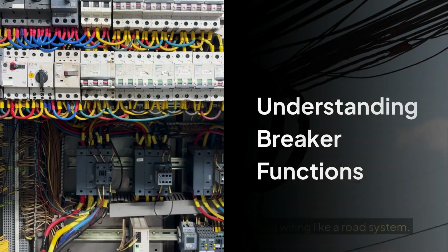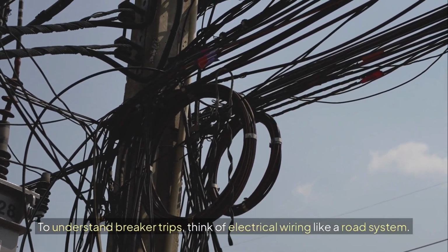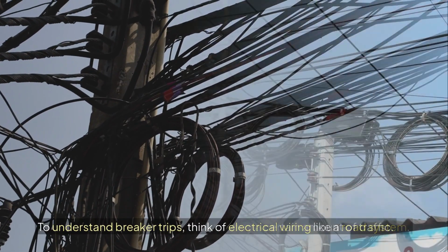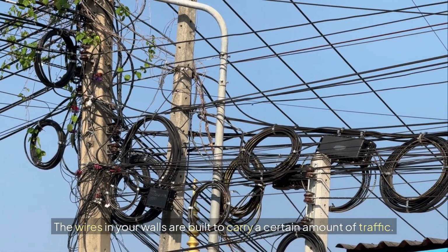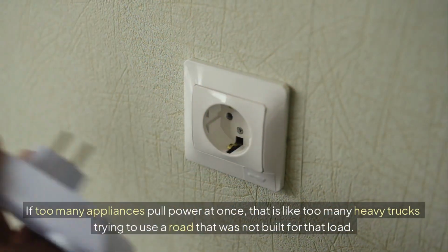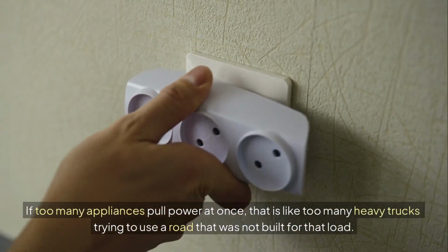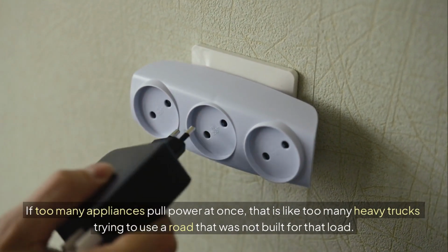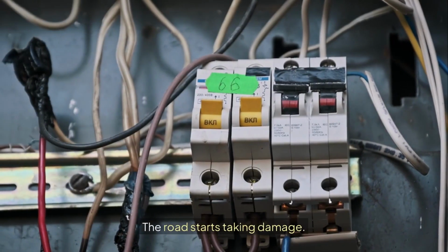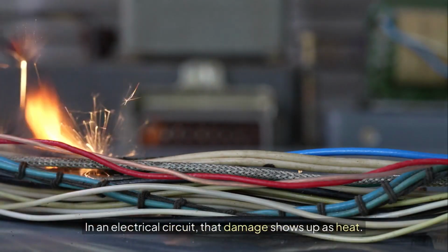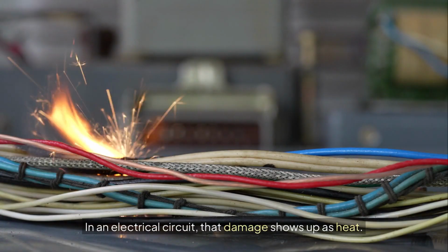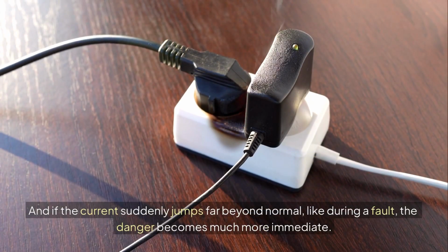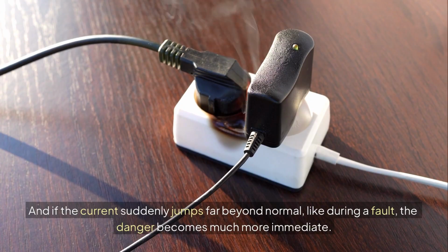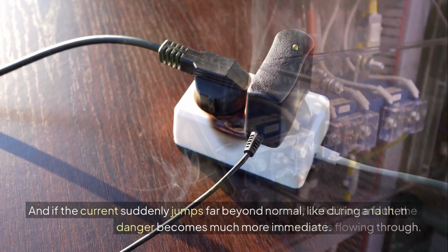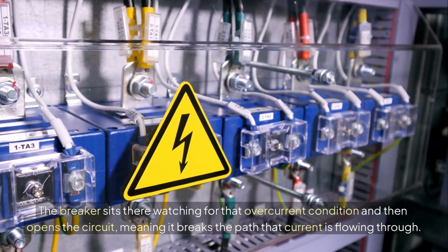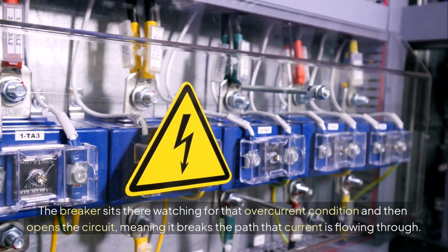What a breaker is really doing: to understand breaker trips, think of electrical wiring like a road system. The wires in your walls are built to carry a certain amount of traffic. If too many appliances pull power at once, that is like too many heavy trucks trying to use a road that was not built for that load. The road starts taking damage. In an electrical circuit, that damage shows up as heat. And if the current suddenly jumps far beyond normal, like during a fault, the danger becomes much more immediate. The breaker sits there watching for that overcurrent condition and then opens the circuit, meaning it breaks the path that current is flowing through.